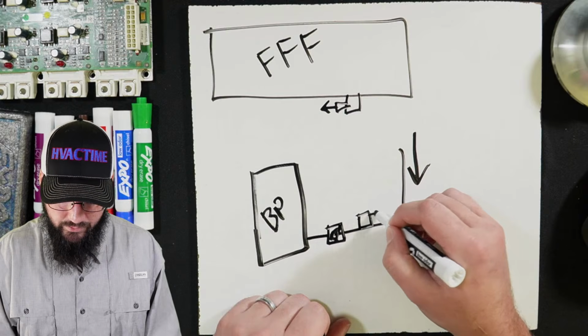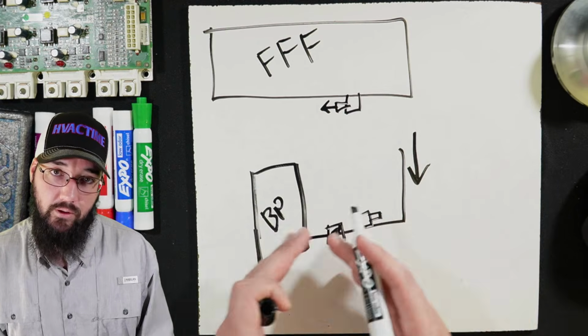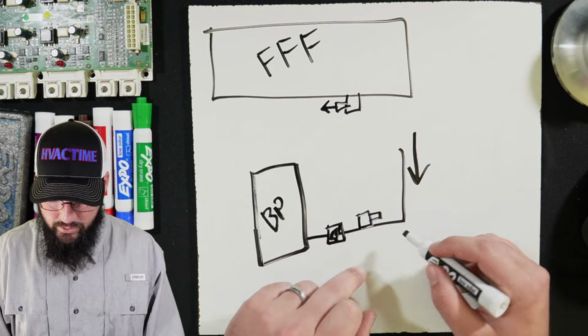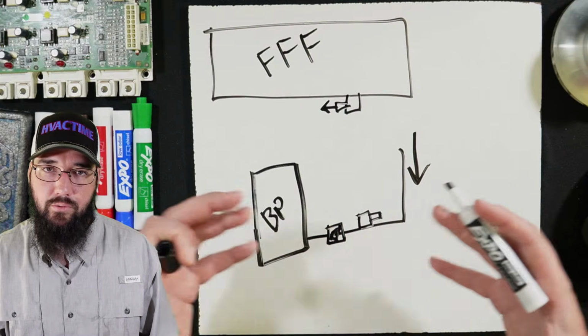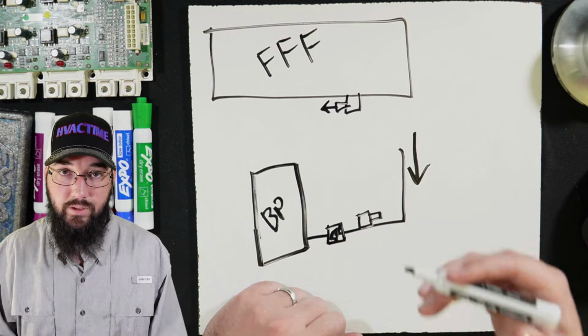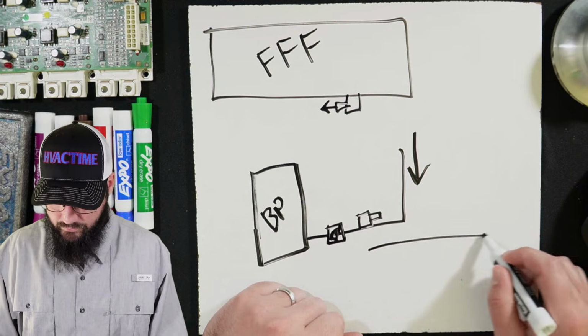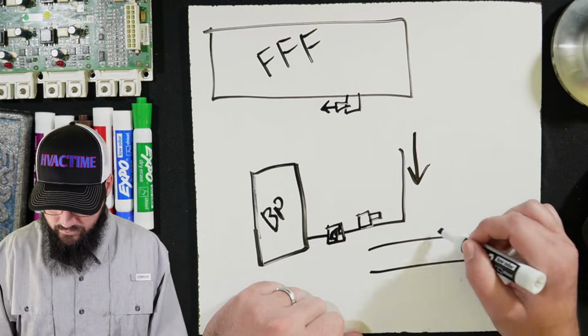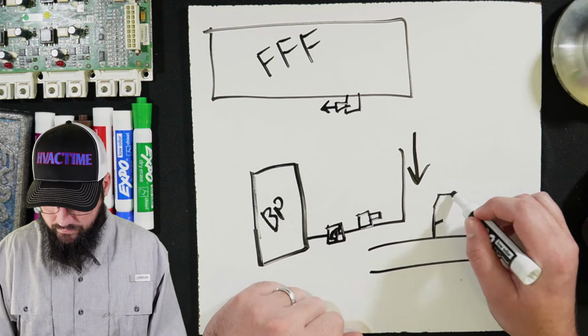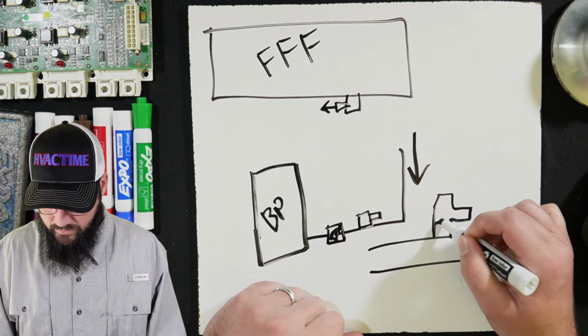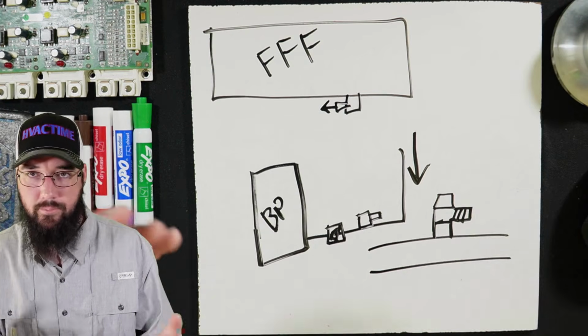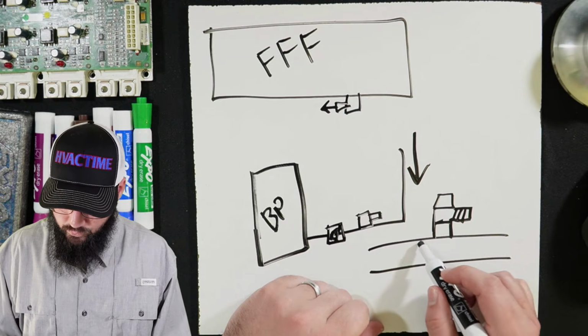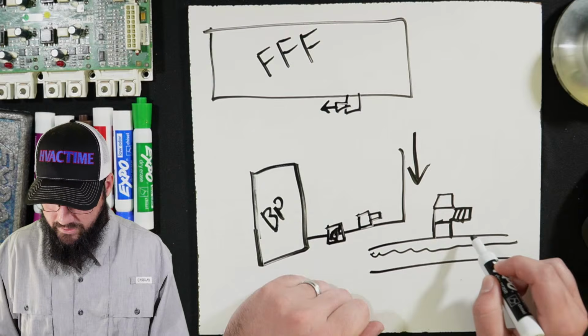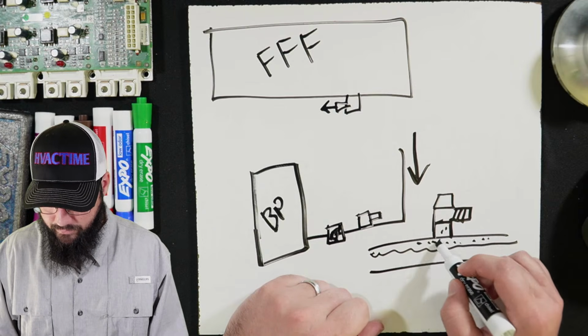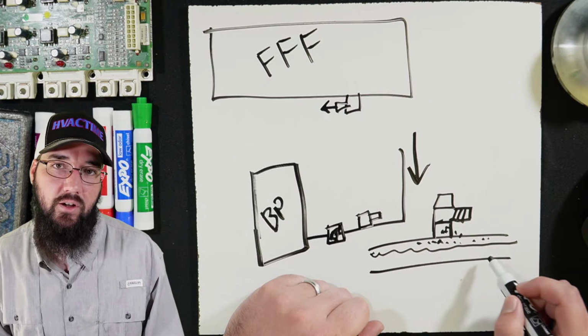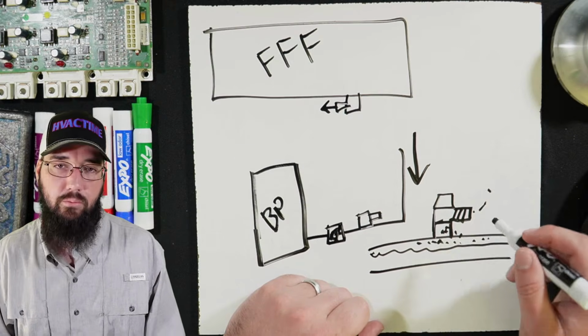So it's coming down from the condenser. So that's our liquid line flowing in. The problem is it's right on the top of the pipe. When we start dealing with all of that stacking on top of the pipe, that's when we really start getting into trouble. Because if you think about it, when our service valve is up here, okay, just imagine that's a valve. There's your threads, whatever. Once that liquid refrigerant gets down past a certain point, we're only pulling vapor, and there can still be a lot of liquid stuck in that pipe, but not actually making it out of the port.